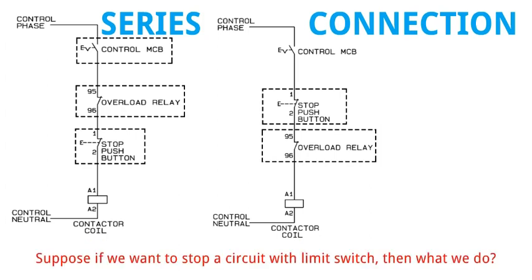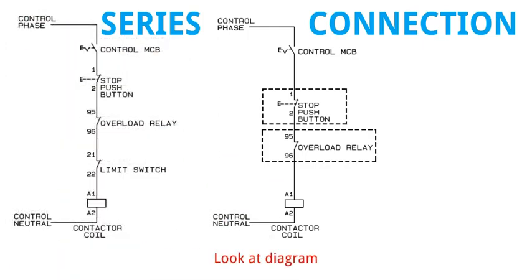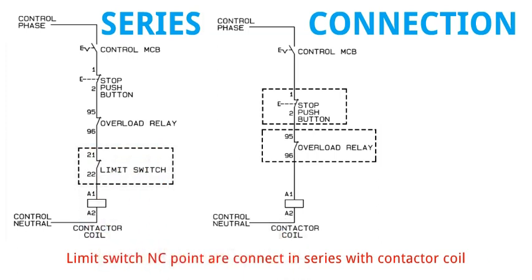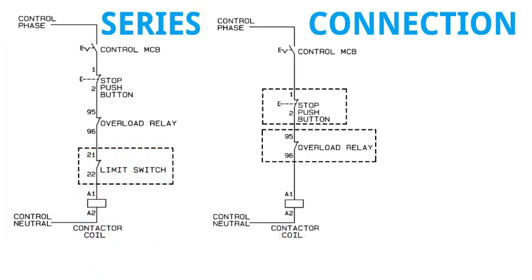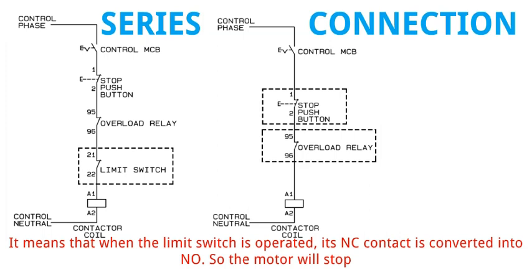Suppose if we want to stop a circuit with limit switch, then what we do? Look at diagram. Limit switch NC point are connected in series with contactor coil. It means that when the limit switch is operated, its NC contact is converted into NO. So the motor will stop.